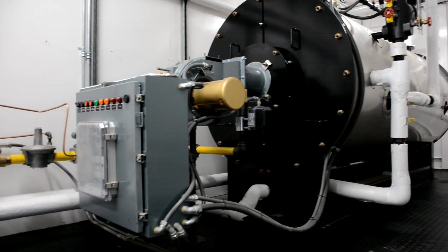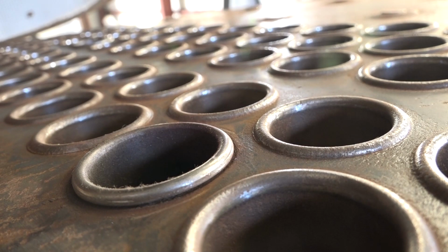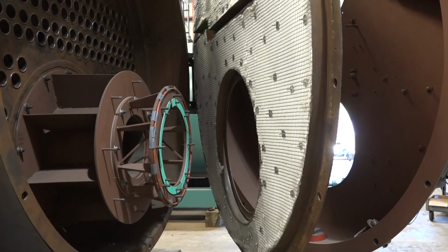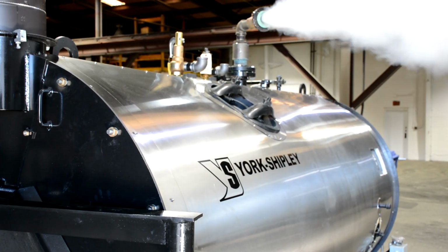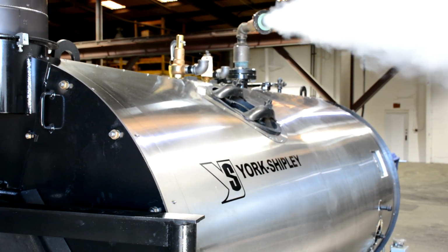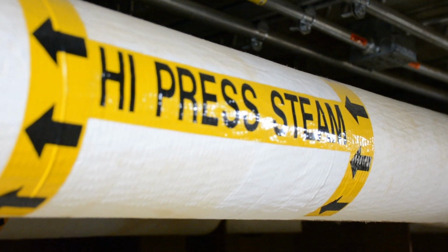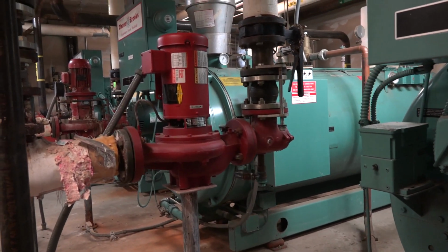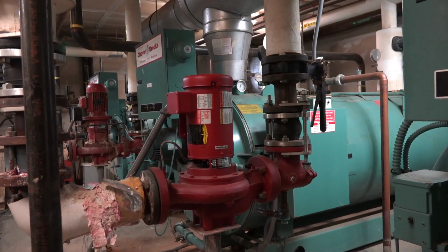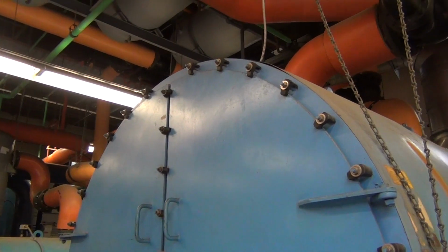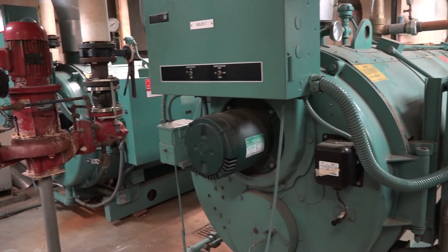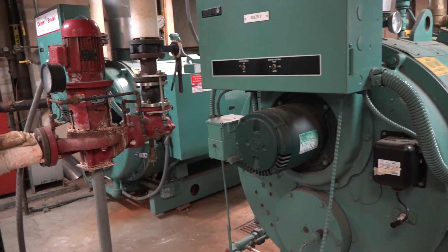At a glance, a fire tube boiler, whether hot water or steam, looks very similar to one another. However, there are some differences to note. So first, it's important to understand that steam pressure will travel the path of least resistance, and hence steam systems will traverse the piping without any need for pumps for circulation. Contrary to this, a hot water boiler needs an installed pump on the outlet of the system to carry the heated water on its intended path. Other accessories that are common to hot water boilers could be air vents, water pressure regulators, backflow preventers, expansion tanks, and of course hot water rated pressure relief valves sized for the boiler.